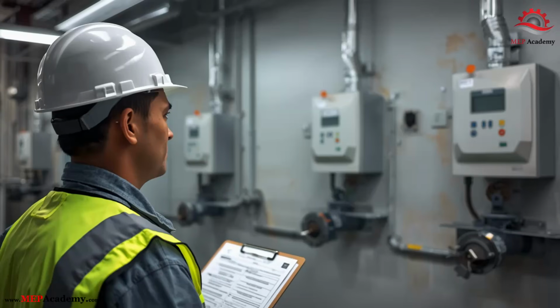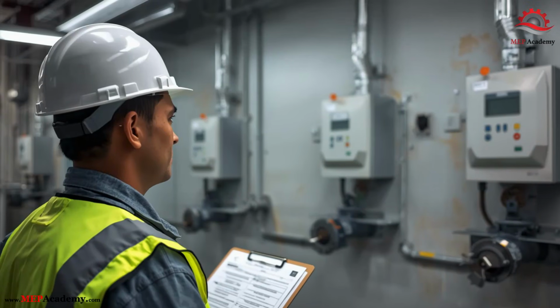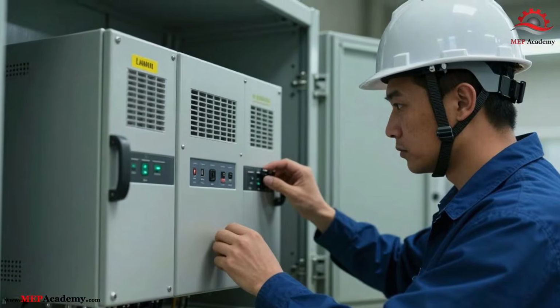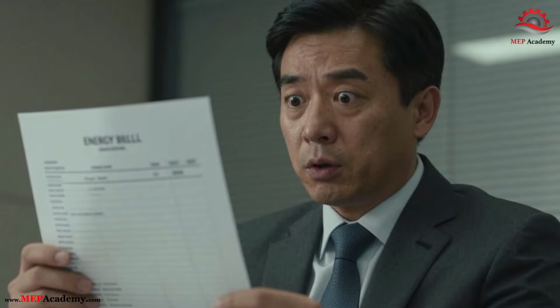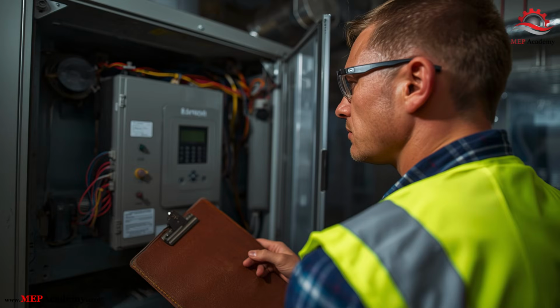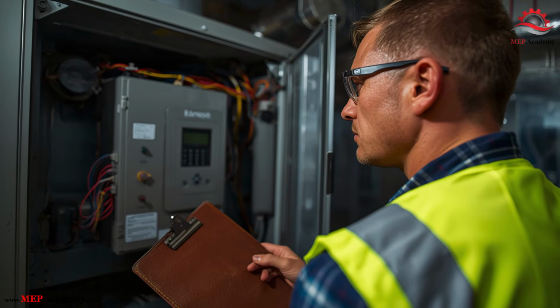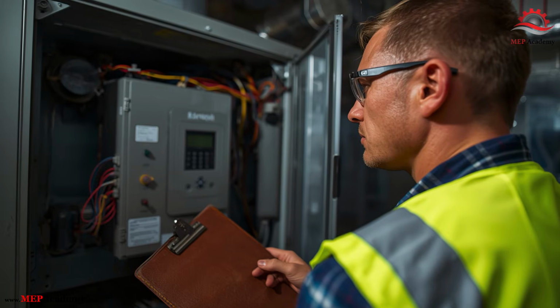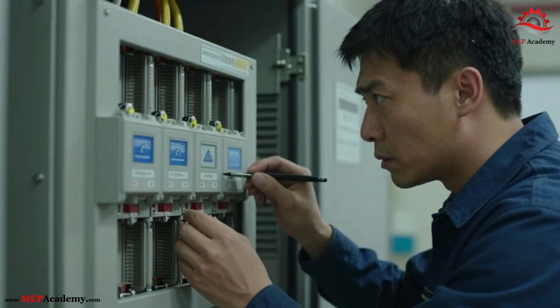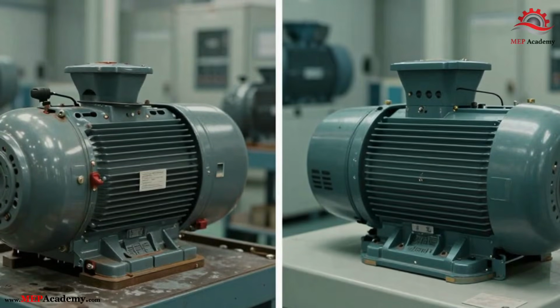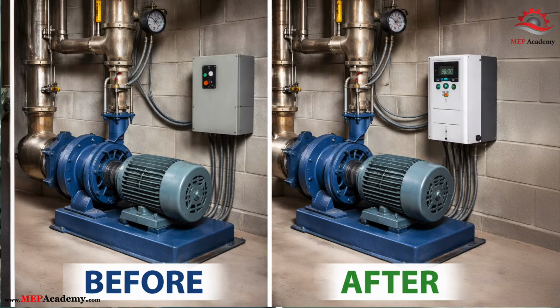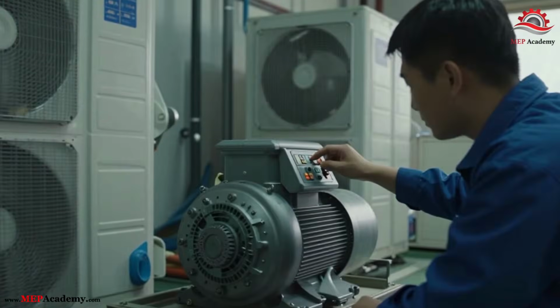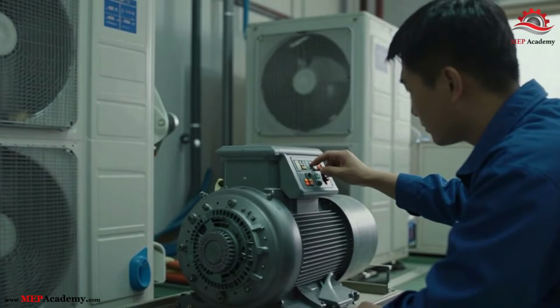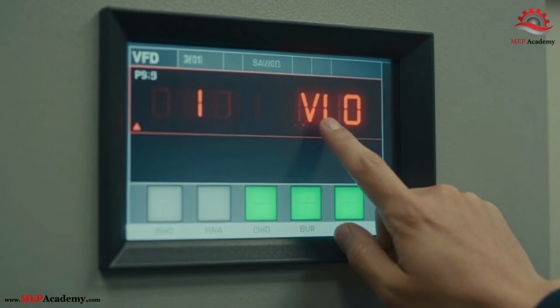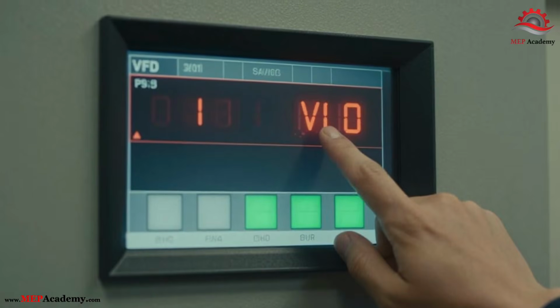Variable frequency drives are one of the most common energy retrofit recommendations in commercial buildings. Utilities love them. Owners expect big savings. But in the real world, a lot of VFD retrofits don't deliver what was promised. Or worse, they create comfort, controls, and maintenance problems. In this video, we're going to walk through two real-world VFD retrofit examples and show a clear before and after comparison for each one. These are common situations you'll see in existing buildings, and we'll focus on what changes in the system, how the controls work, and where the energy savings really come from.